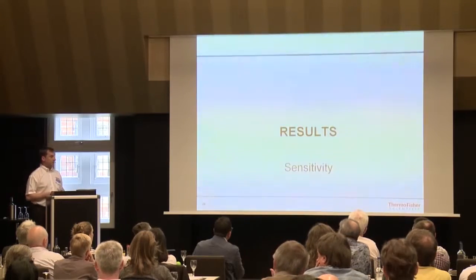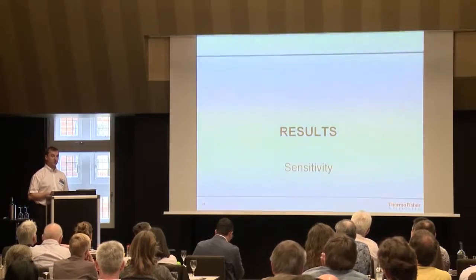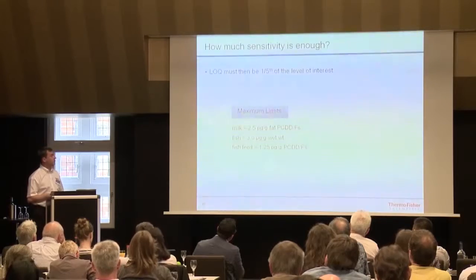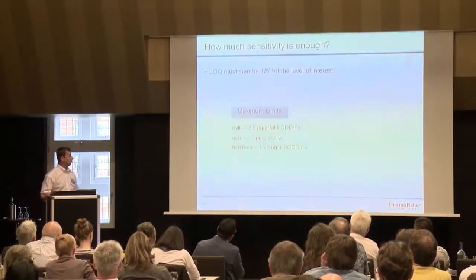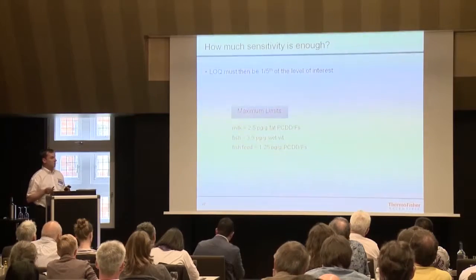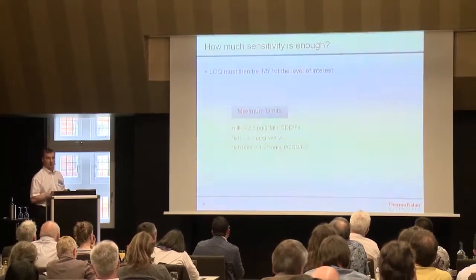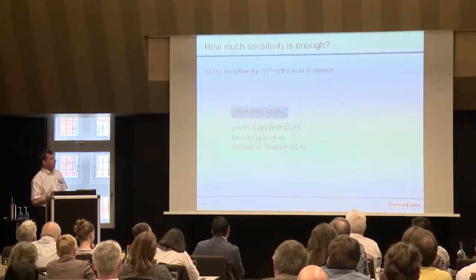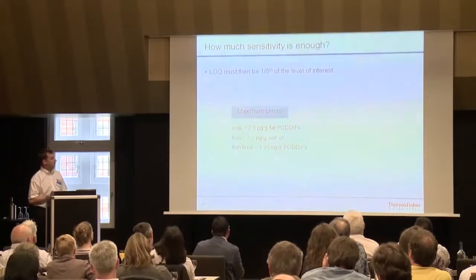The next question is how sensitive such an instrument is for dioxin analysis. Having a very sensitive instrument is a great thing, but you have to keep in mind that you must meet all the criteria — ion abundance within range, response factor within range. We're aiming for at least one-fifth of the level of interest, which is normally the maximum limits, and those are matrix dependent.